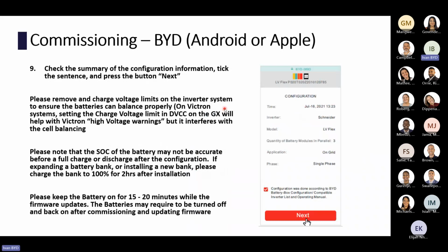Just a little note: if you can, please remove the charge voltage limits on DVCC on the Victron systems. You won't be able to get the batteries balanced if DVCC is on. There is a document on the Victron site that explains how to minimize high voltage warnings, but in doing so, it disables the battery's ability to cell balance and SoC calibrate. So it's best to remove the charge voltage limit on DVCC.